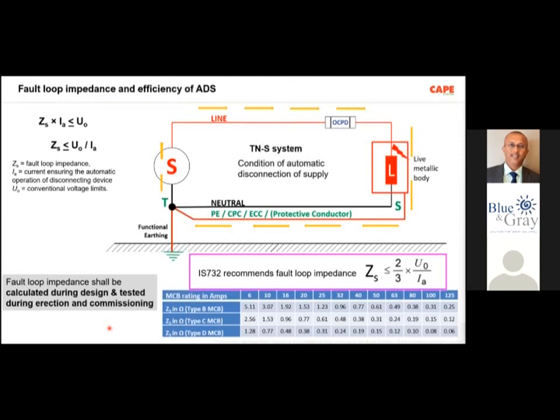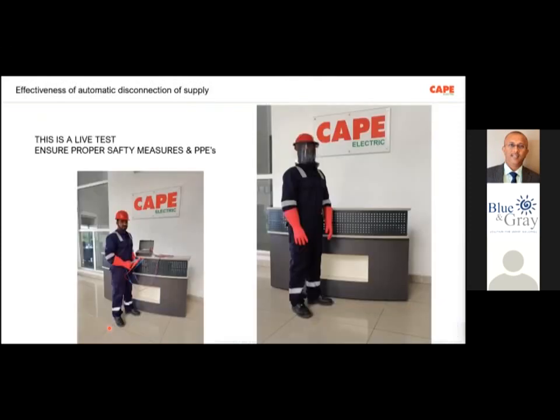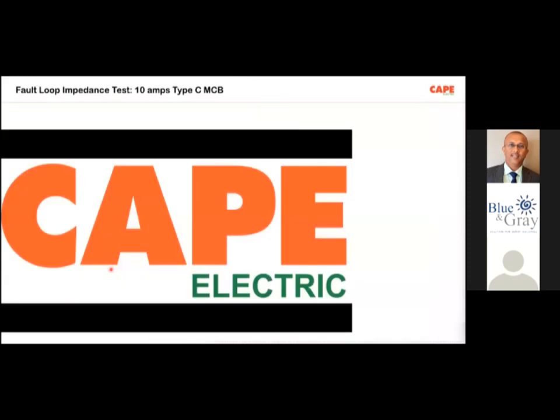So what I wanted to tell you is, if you are doing an electrical safety audit, first try to understand what it is, and then you do it. If you don't understand, and you go with a meter and try to test it, it won't work out. Now, the fault loop impedance test is a live test. Your supply has to be in on condition, your transformer must be on, your DG must be on, and then you should do it, and you have to be very careful. You have to have the proper PPE to do the test if you are opening a live circuit, especially a distribution board. Now, I'm showing you a test which is carried out again in our facility.